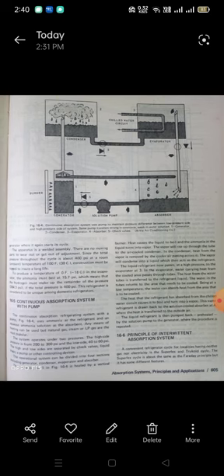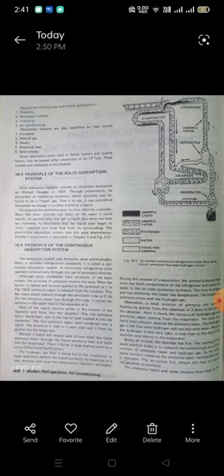The air-cooled absorber fins help cool the weak solution, which helps it reabsorb the ammonia gas out of the ammonia vapor and hydrogen gas mixture. As heat is liberated, the air-cooled fins remove this heat to permit refrigeration to continue. The ammonia and water mixture flows back to the generator, where the cycle starts again. There are no moving parts to wear out. The total pressure throughout the cycle is about 400 psi at an ambient temperature of 100°F (38°C). To produce a temperature of 0°F (-18°C) in the evaporator, the ammonia must boil at 15.7 psi.